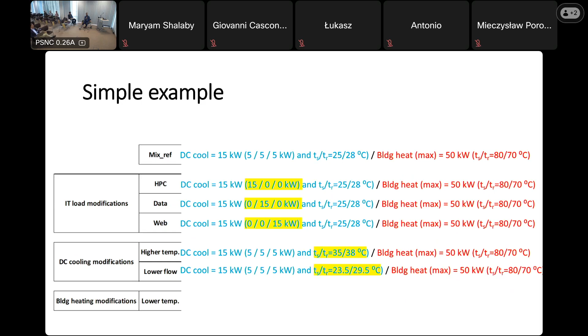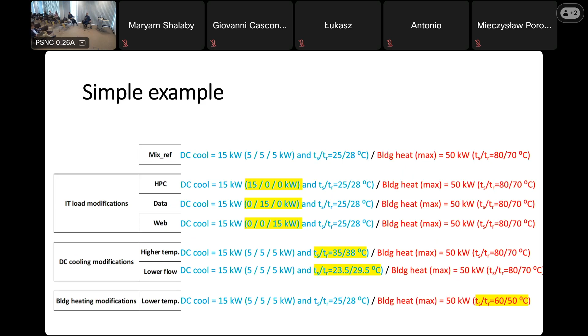And the last case, we modify the building heating system, so we just change the heating curve, using a lower temperature in the heating curve, but the power of the heating system stays the same. For example, a higher area of radiators in the building gives the possibility of decreasing the temperature.